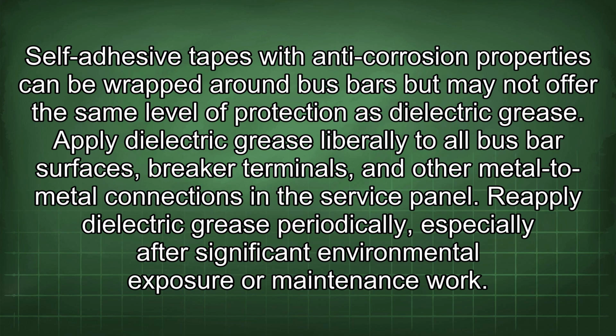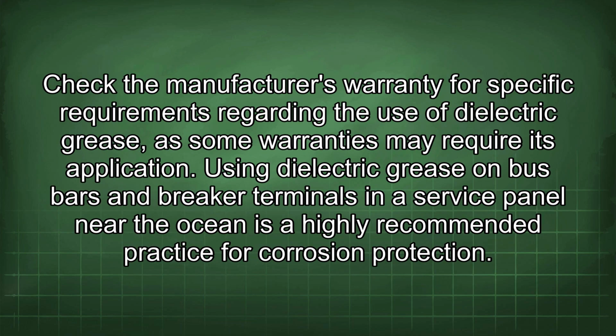service panel. Reapply dielectric grease periodically, especially after significant environmental exposure or maintenance work. Check the manufacturer's warranty for specific requirements regarding the use of dielectric grease, as some warranties may require its application.